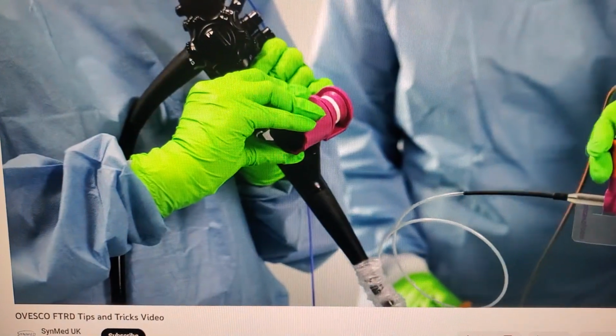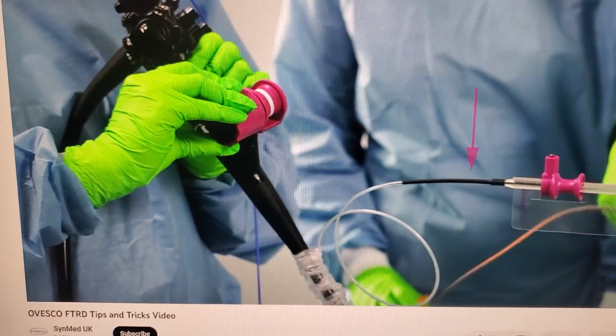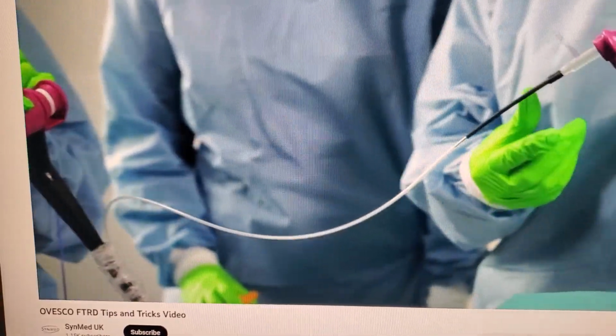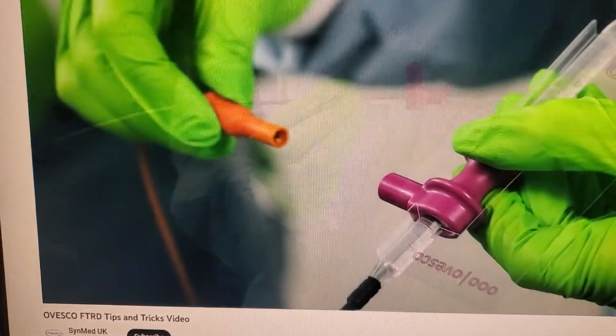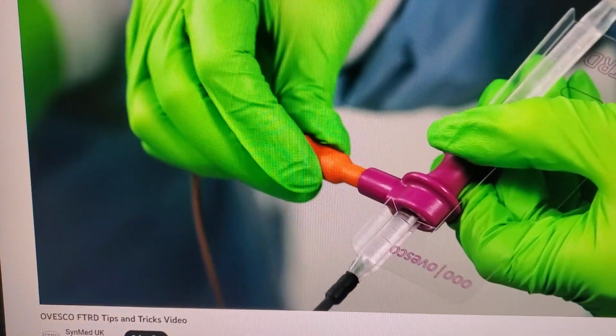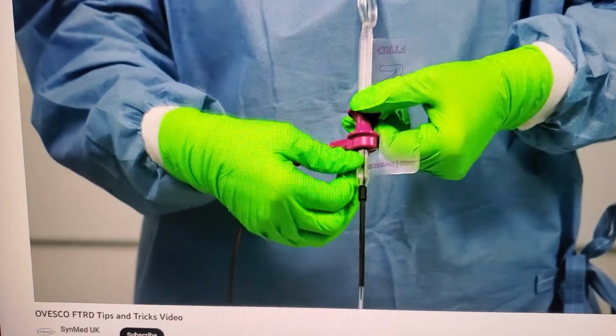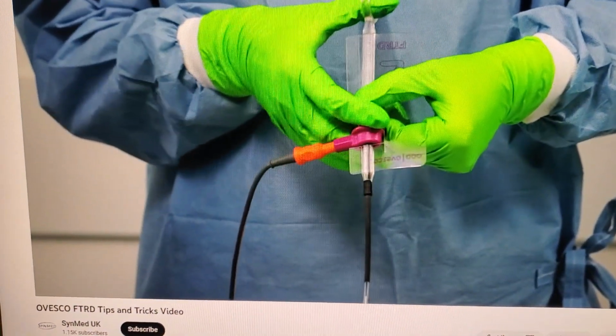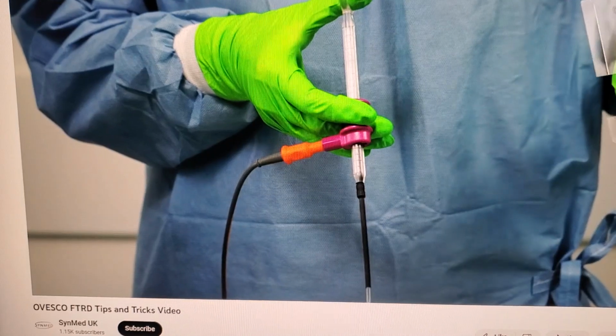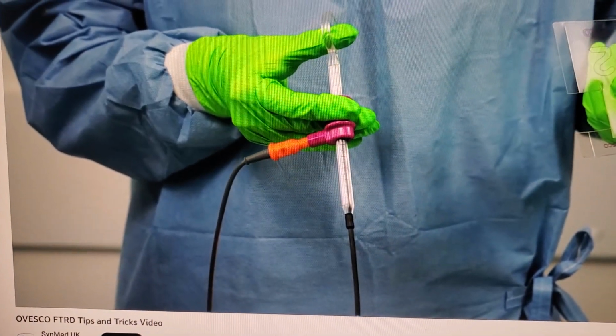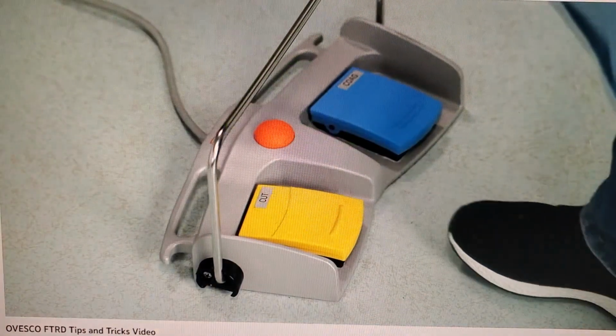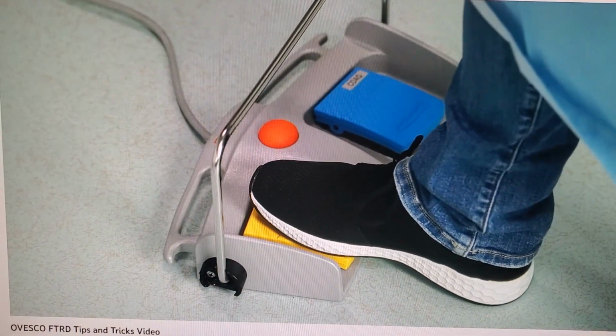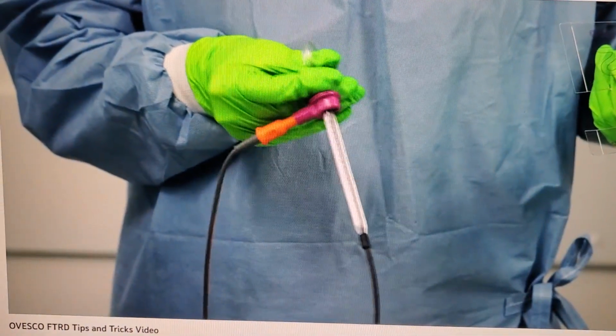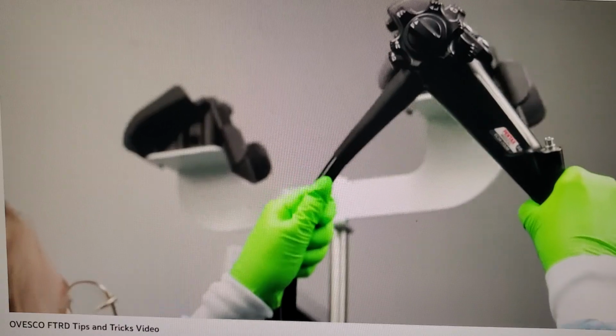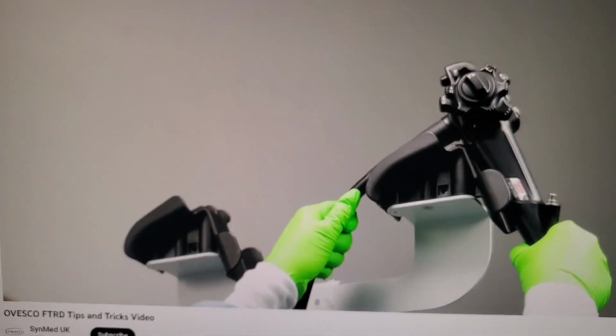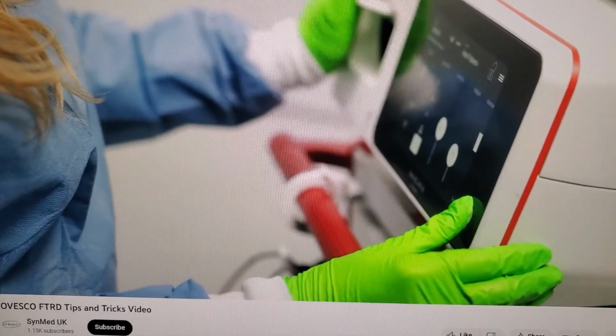The part of the snare shaft that is not inserted, especially the black bordered area above the handle, must be as straight as possible and not kinked or coiled. Otherwise, this can make snare closure difficult or even impossible. After the clip has been applied, give the command to release the snare safety lock. Pull the sliding handle backwards until resistance is reached, and hold it in this position. Activate the HF current for the final resection after the snare is securely closed around the tissue. After resection of the captured tissue, retrieve the specimen from the patient by removing the endoscope while keeping the FTRD grasper closed.